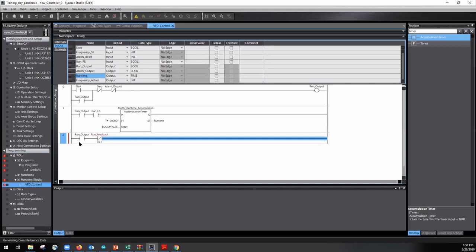What was the reason for the bool on the reset? Oh, I put bool pound false. Is that no reset for that timer, just constantly running? Yeah, it's more of an OCD thing with me. I could leave that blank if I wanted to. It's false by default. I like to populate all input parameters, but I could just leave it blank. It defaults to 0. I'm also trying to drill into people how Omron does constants versus other people. You have to specify the data type name and then pound and then the value. Same with the timer here, T pound 10,000 days.